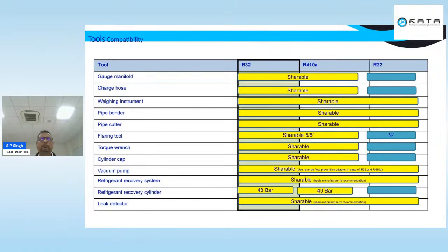We should start using a torque wrench when carrying out the flaring. Everybody is carrying out the flaring and tightening the flare nut with an adjustable wrench. You can adjust the adjustable wrench, but it is better that you start using a torque wrench, because the torque is set as per the piping design. Based on that, your flare won't get damaged, and refrigerant leakage will be very less.